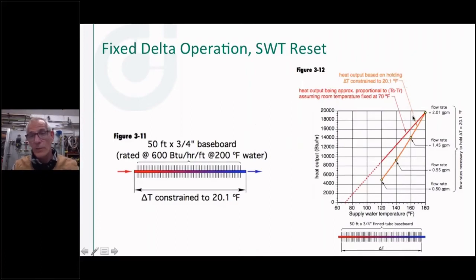Here's one thing I want you to be aware of when you do that. So this line up here is what would happen if it was just allowed on a reset control to operate at fixed speed on the circulator. This orange line, if you look what happens here, is the flow rate's changing, and it's changing because the flow rate's trying to match that delta T that you programmed into that circulator pump. And so you're fine, as long as you know that when you start getting down to these low supply temperatures where your boiler's ramping down on its outdoor reset and the circulator's still trying to maintain that 20-degree delta T, you can see that your output's going to drop off pretty quickly. In fact, when you get down to this point right here, you've got about 50% less output by modulating that speed, that flow rate down, as opposed to just letting the temperature go down in that loop. So just beware of that.